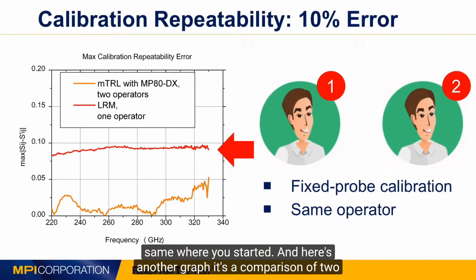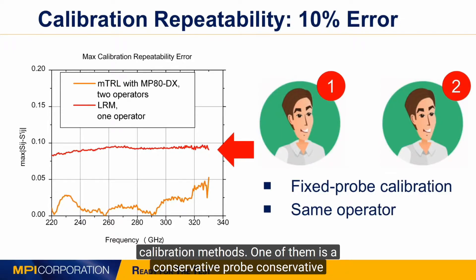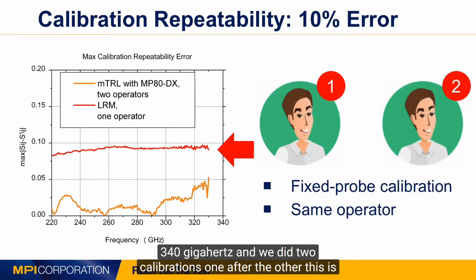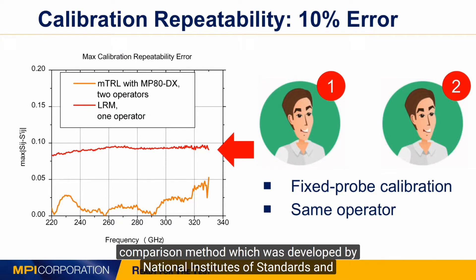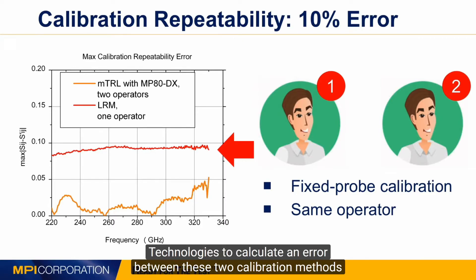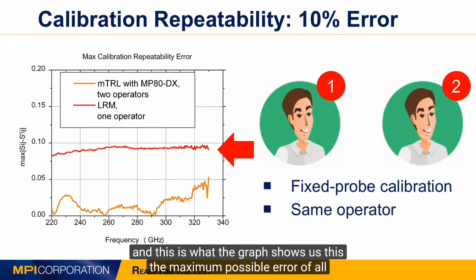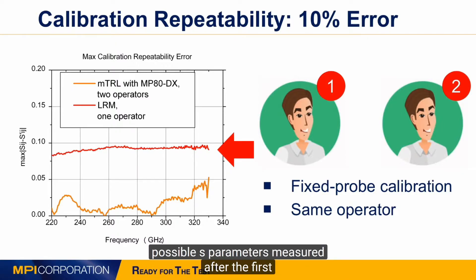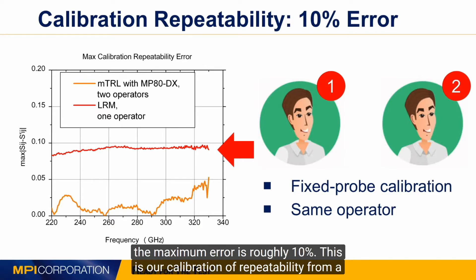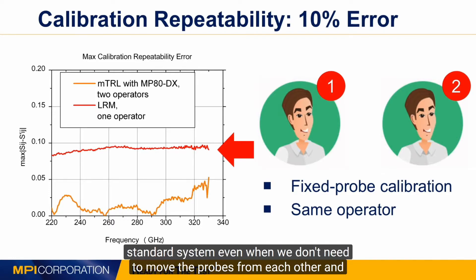Here's a comparison of two calibration methods. We took an LRM standard at frequencies from 220 to 340 gigahertz and performed two calibrations one after another to assess reproducibility. Using the calibration comparison method developed by the National Institute of Standards and Technology, we calculated the error between the two calibrations. The graph shows the maximum possible error across all four S-parameters after the first calibration versus the second. The maximum error is roughly 10% — that is our calibration repeatability on a standard system, performed by a single operator.